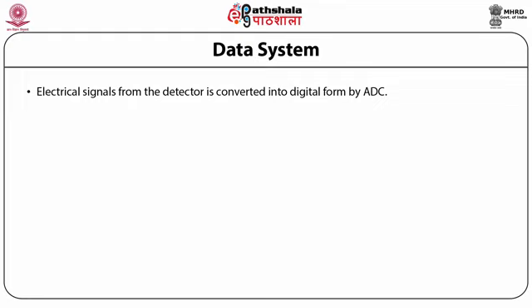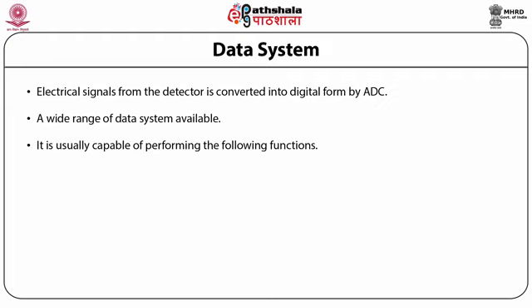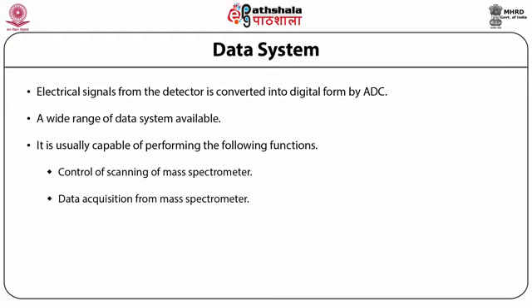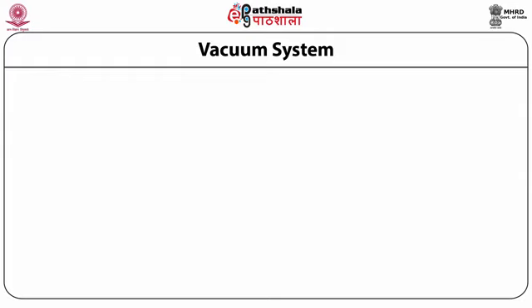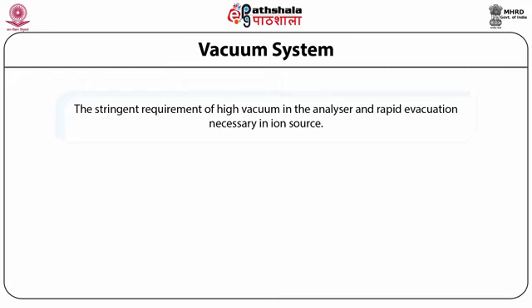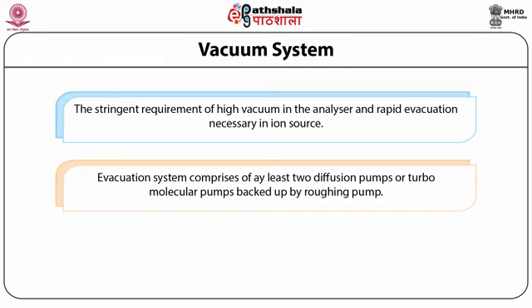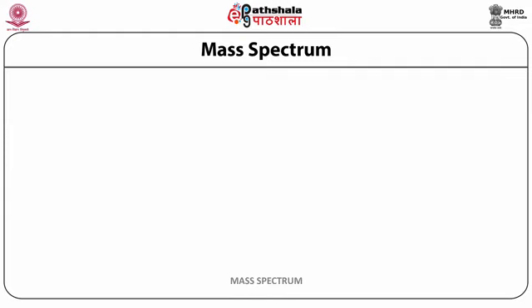The data system: electrical signals from the detector are converted into digital form by an ADC. A wide range of data systems are available, capable of performing control of scanning of the mass spectrometer, data acquisition, and data processing. The mass spectrometer works under a very high vacuum because the ions formed have to travel to the detector, and if the system is not under high vacuum the ions will collide with each other and nothing will be recorded. The evacuation system comprises at least two diffusion pumps or turbomolecular pumps backed up by a roughing pump.